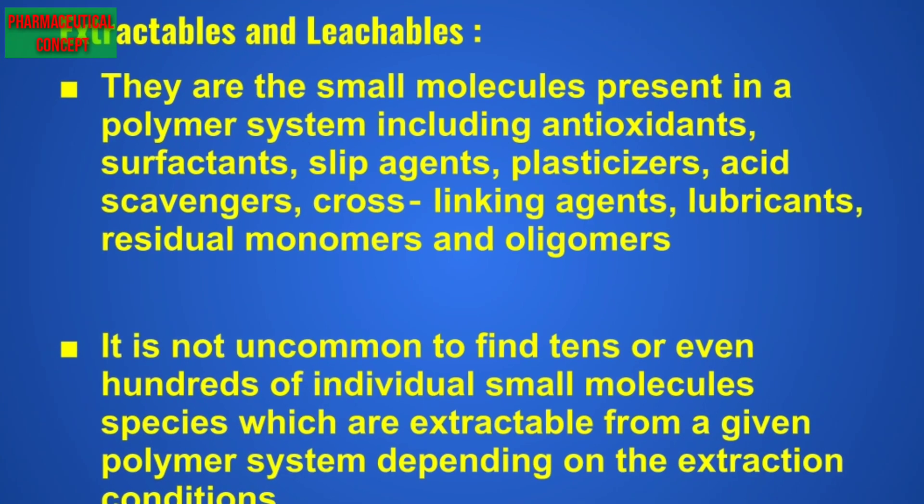Extractables and Leachables are small molecules present in the polymer system, including antioxidants, surfactants, slip agents, plasticizers, acid scavengers, cross-linking agents, lubricants, residual monomers and oligomers. It is not uncommon to find tens or even hundreds of individual small molecule species which are extractable from a given polymer system depending on the extraction conditions.